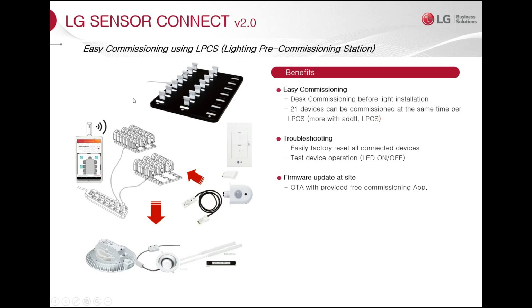You can actually dim those LEDs and see them changing when you're making changes. This gives you the ability to program these dongles and sensors before they get installed into the lights. It's also a great training tool — you can carry this around with you in a laptop bag, and you essentially have 21 fixtures in your bag, simply powered by a USB cable. So very simple, lightweight, convenient, and gives you the ability to either troubleshoot problematic devices or program something before it gets installed.